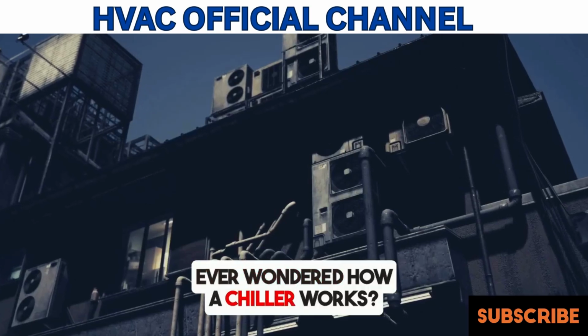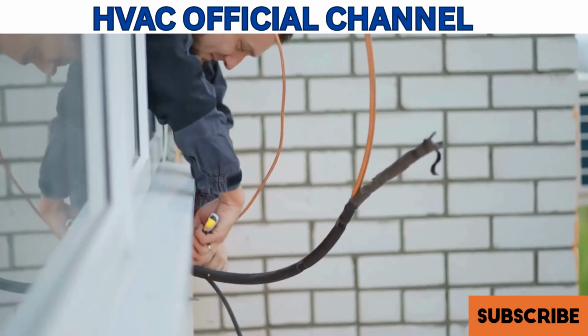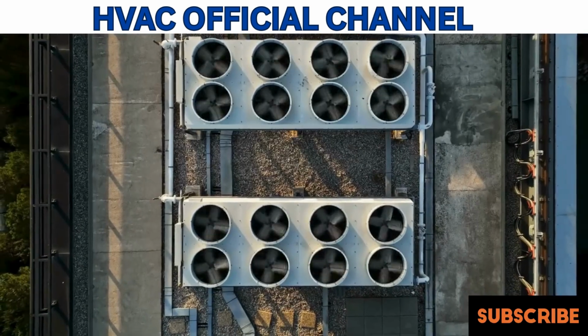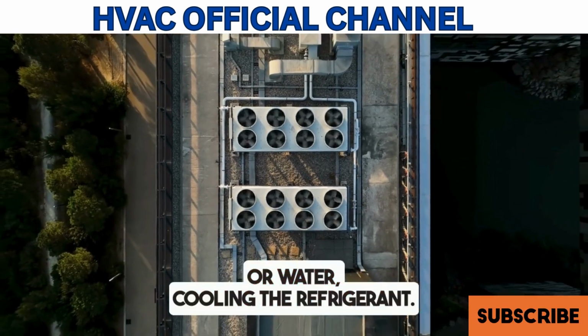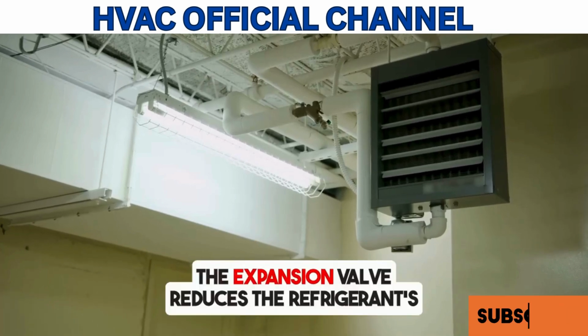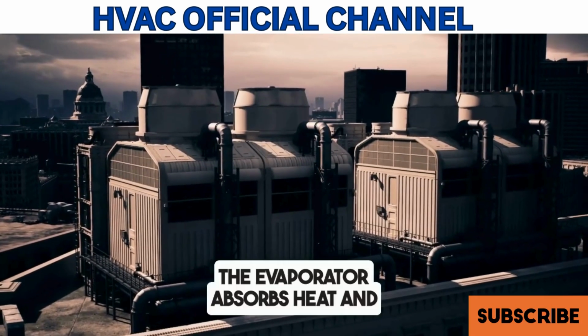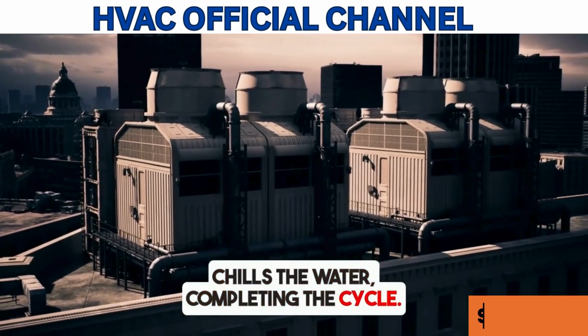Ever wondered how a chiller works? Let's break it down step by step. Step 1. The compressor compresses the refrigerant, increasing its pressure and temperature. Step 2. The condenser rejects heat to air or water, cooling the refrigerant. Step 3. The expansion valve reduces the refrigerant's pressure, preparing it for cooling. Step 4. The evaporator absorbs heat and chills the water, completing the cycle.